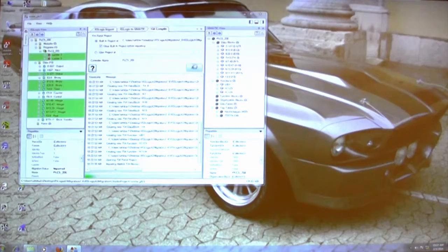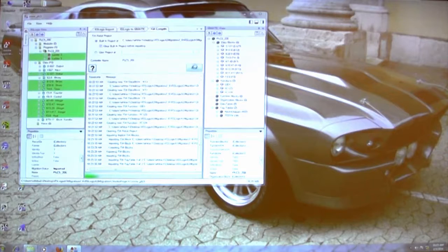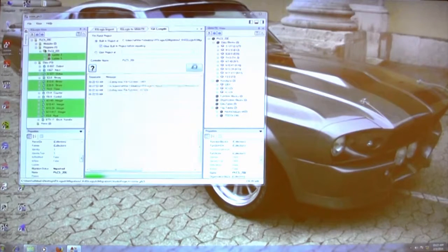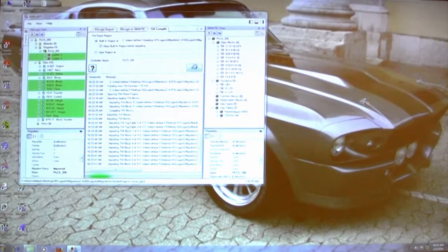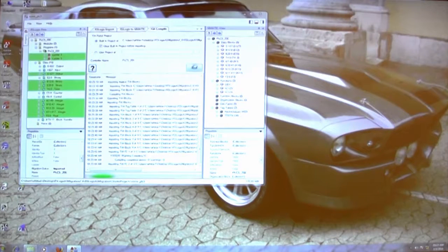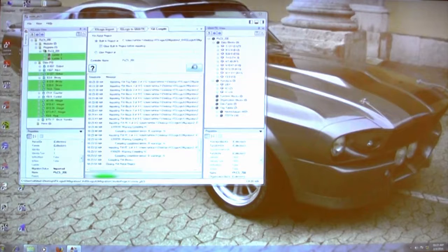So if I'm in the Logix environment, there's a couple extra things that happen on the right in the tool. One, add-on instructions get converted to function blocks. And every time we have a function block, it creates the associated data block. Two go hand in hand. In Logix, I have data types, UDTs. We create the data types on the right. So that would be an extra thing you would see if we were converting a Logix program.